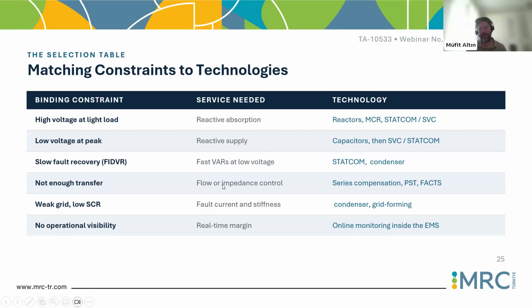So even if it is weak and has such extra stuff, you should control the voltage, in this case maybe not the reactive power, very fast and also sustain the renewable generation. So synchronous condensers are one of the important kinds of equipment. They could be expensive, or you have to find a place for them to use. In Europe, I heard, I didn't work directly on it, that thermal power plants can be converted to synchronous condensers.